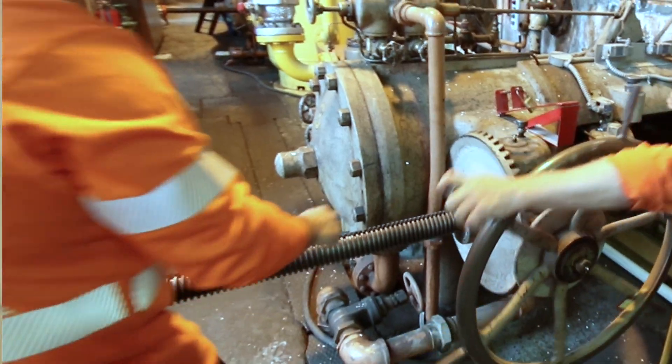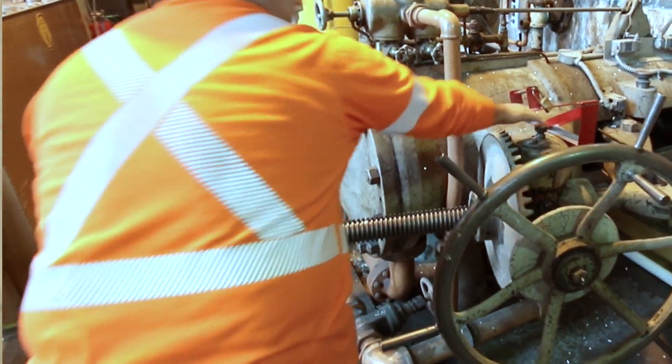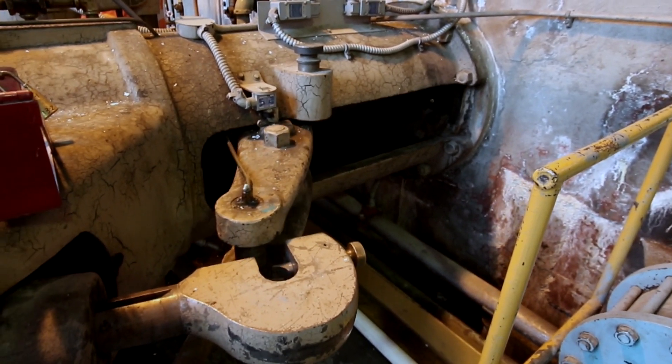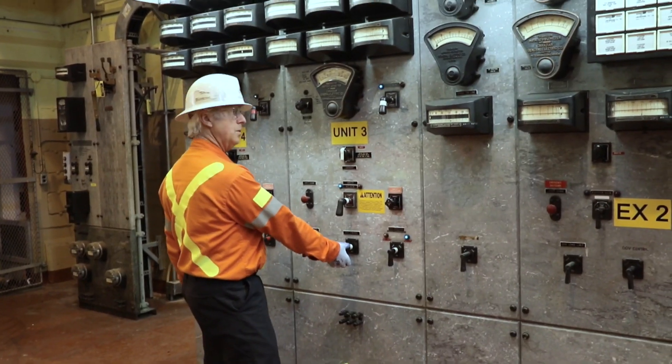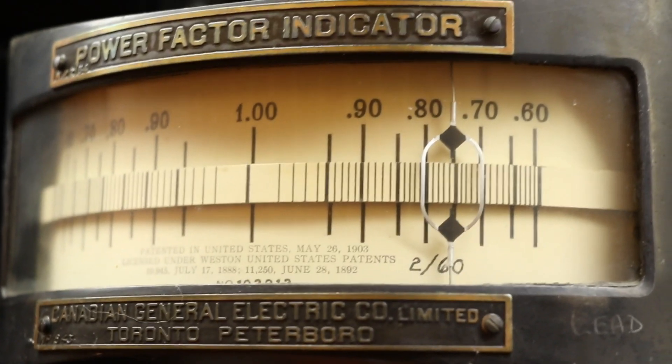Once the cooling water is flowing, two tradesmen are required to manually turn the hand wheel to free the governor arm. They then manually open the wicket gates to set the unit speed to 179 RPM. Unlike our newer units which are all controlled remotely, this unit has to be manually synchronized online.